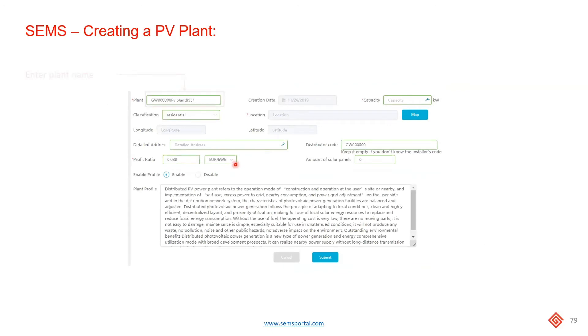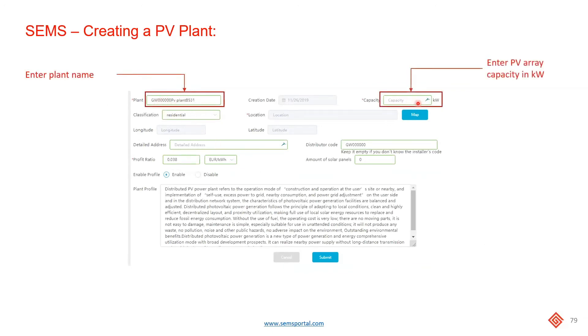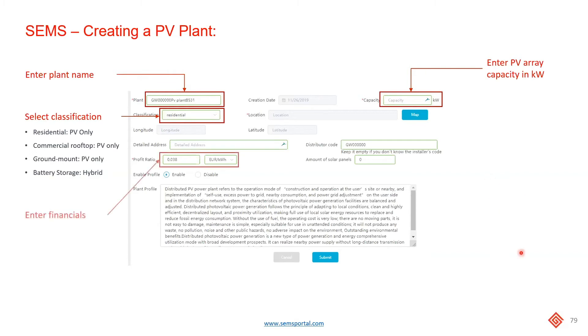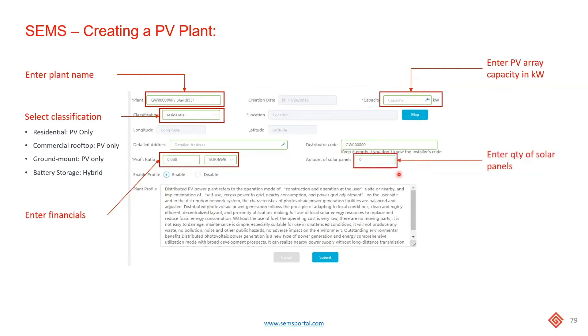After you've done that, enter a name for the PV plant and enter the capacity in terms of kilowatts. Select the right classification — if it's for hybrid inverters, make sure that you select battery storage, as this will show the correct graphs on the PV plant overview page. You can also enter the financials, which is generally the cost of electricity for that particular end user, and the number of PV panels.